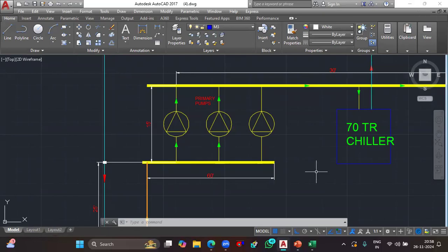Sir, to brief in short, based on tonnage, pipe length and flow rate, we are finding the HP of the pump. Right, sir? Yeah, once again, one more thing. It's not meant to be the length, sorry, basically it is meant to be the distance of the piping.